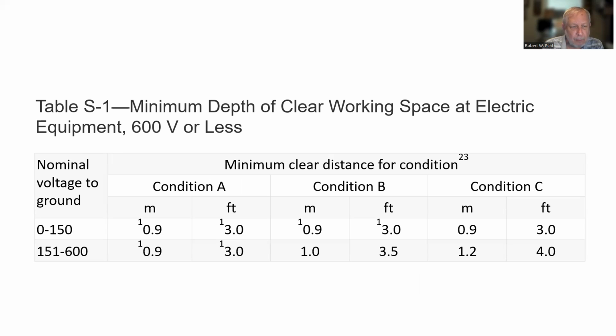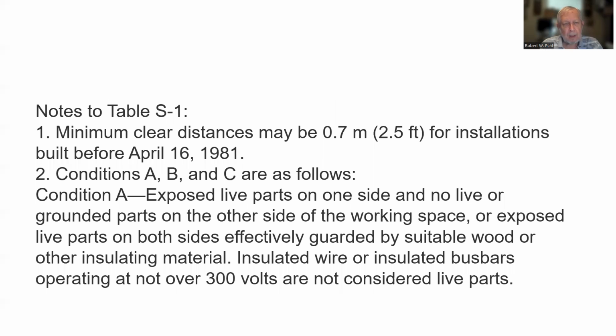So nominal voltage to ground, 0 to 150. Condition A, condition B, we'll talk about this in a minute. So you have 3 feet for condition A, both 3 feet, 3.5 for condition B, and 3 and 4 feet for condition C. So they're not huge differences, but see what these conditions are. Minimum clear distance may be 2.5 feet for installations built before April 16, 1981.